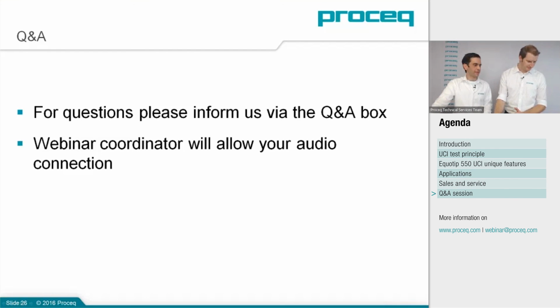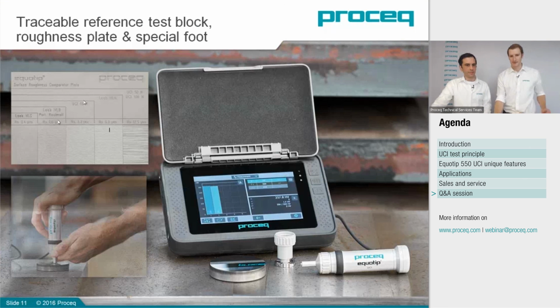I'd like to go back to the accessory slide and show you the roughness comparator plate. I don't know if you can read the values on this plate, but in the middle field, this one is for UCI HV1, and an average roughness of 3.2 micrometers is acceptable. For UCI HV5 on the right side, 12.5 micrometers average roughness is acceptable. As I mentioned, it also depends on the hardness of the material, and these roughness values are for an average steel, which is most often measured with the UCI.